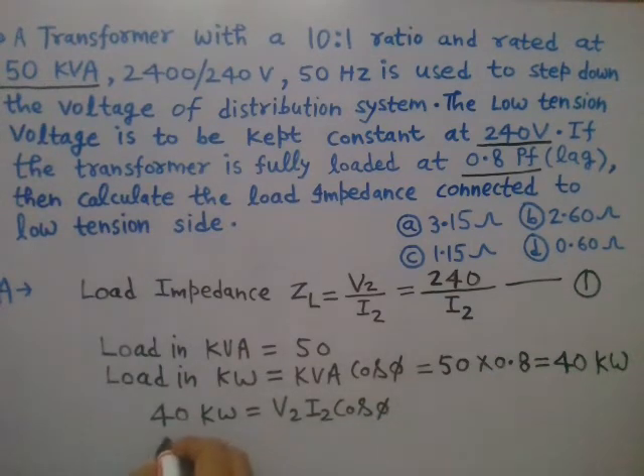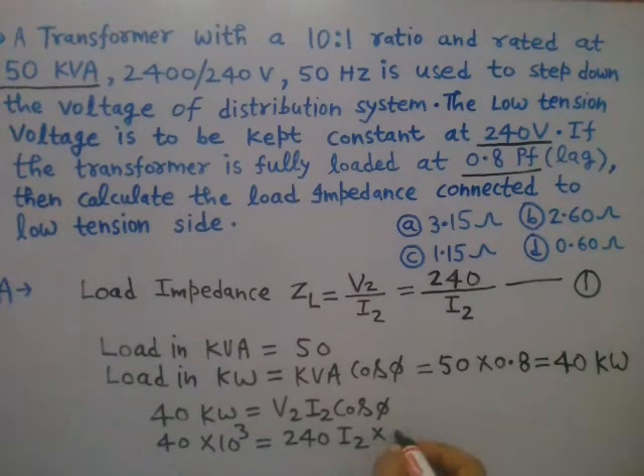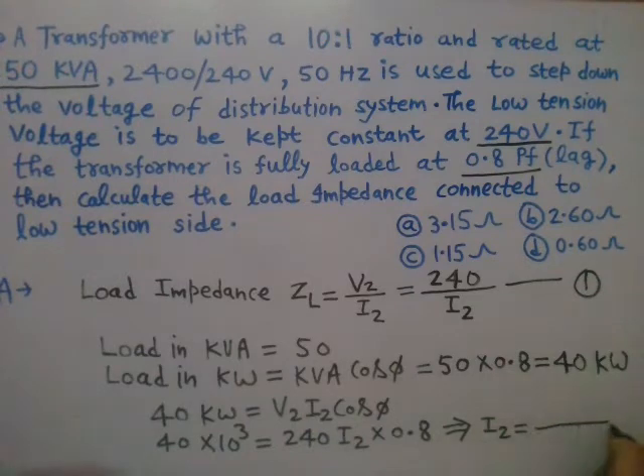Now from here you can calculate I2. 40 kilowatt means 40 into 10 to the power 3 watts. V2 is given as 240 volts, I2 you have to calculate, and cos phi is 0.8. So now you can easily find this load current I2 as 40 into 10 to the power 3 divided by 240 into 0.8.